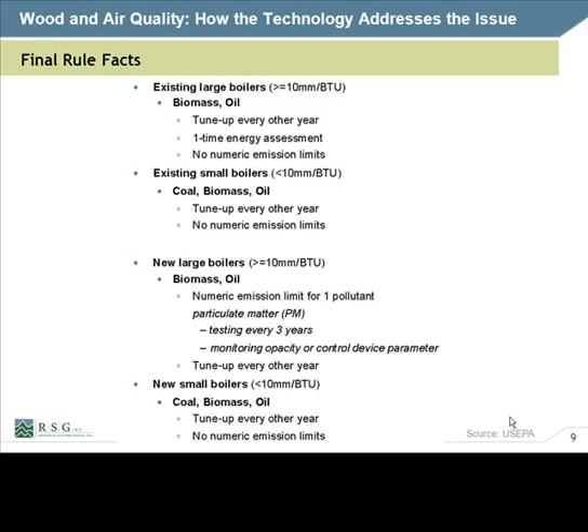One requirement for all boilers is a biennial tune-up, every 2 years, done according to EPA reference methods. There's also a lot of other record keeping, reporting, and paperwork you have to do. So that's just scratching the surface on the boiler MACT rule, or area source rule.